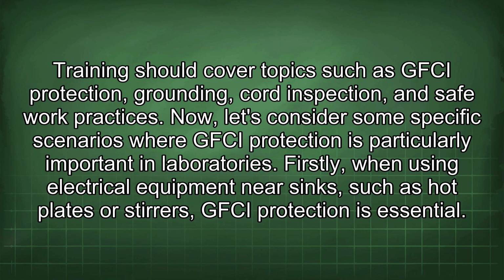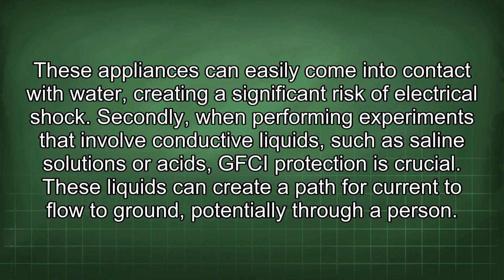Now, let's consider some specific scenarios where GFCI protection is particularly important in laboratories. Firstly, when using electrical equipment near sinks, such as hot plates or stirrers, GFCI protection is essential. These appliances can easily come into contact with water, creating a significant risk of electrical shock. Secondly, when performing experiments that involve conductive liquids, such as saline solutions or acids, GFCI protection is crucial. These liquids can create a path for current to flow to ground, potentially through a person.